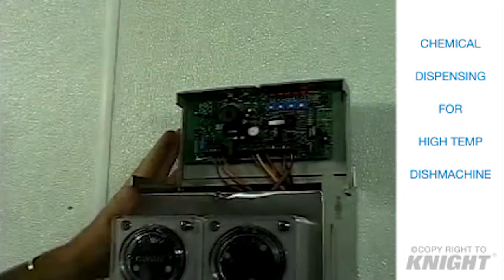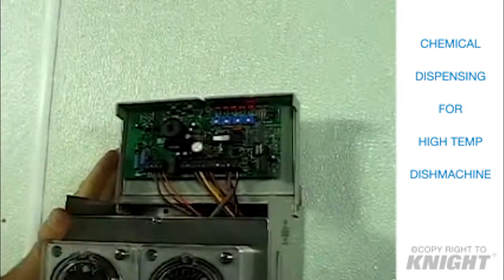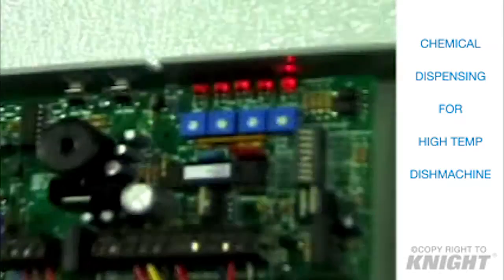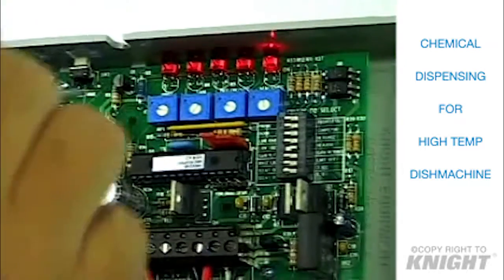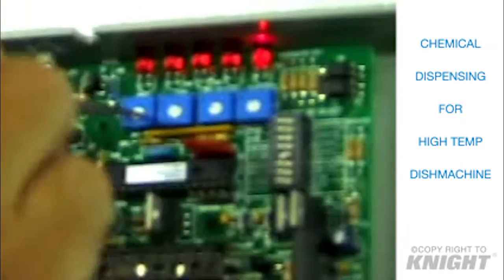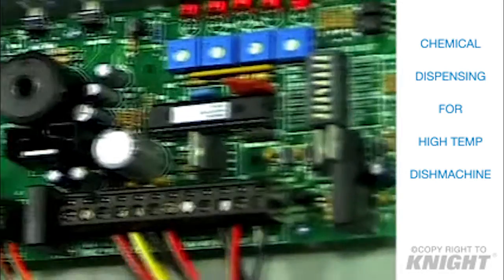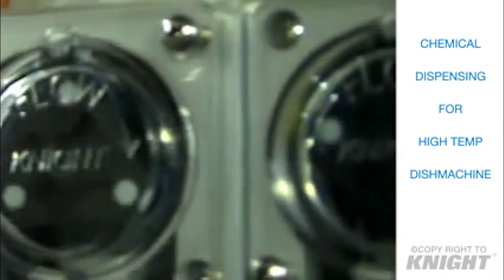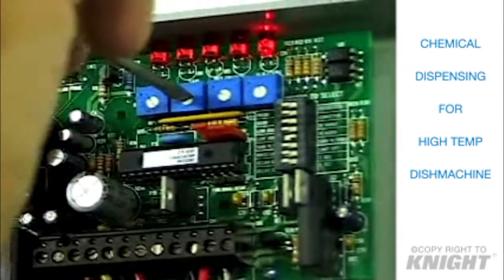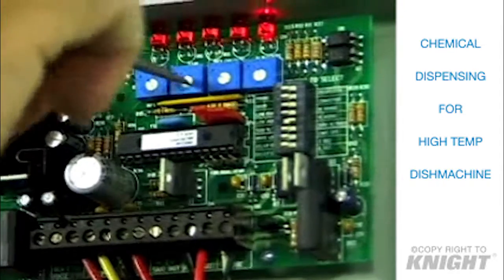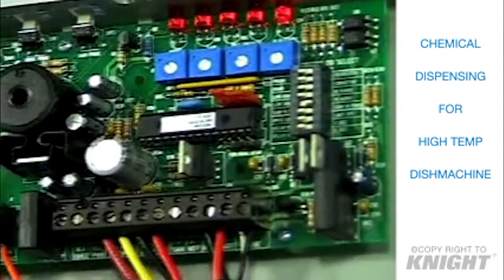Okay, the potentiometers on the MicroPro all are to control either a speed or concentration or time setting. So the rinse adjustment that we just made, the farther I turn this clockwise, the faster the rinse motor is going to run. If I had a sanitizer pump, I'd be able to do exactly the same thing with this potentiometer. But since this unit doesn't have a sani pump, that's not going to be active.